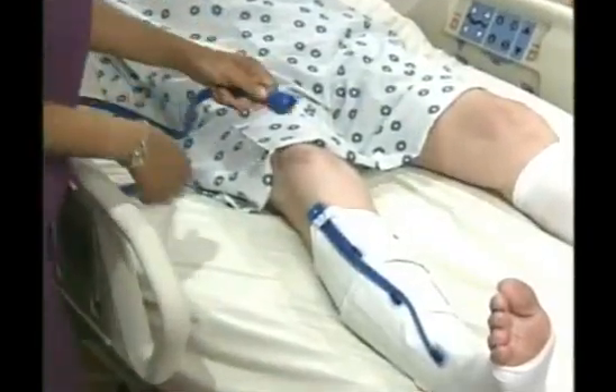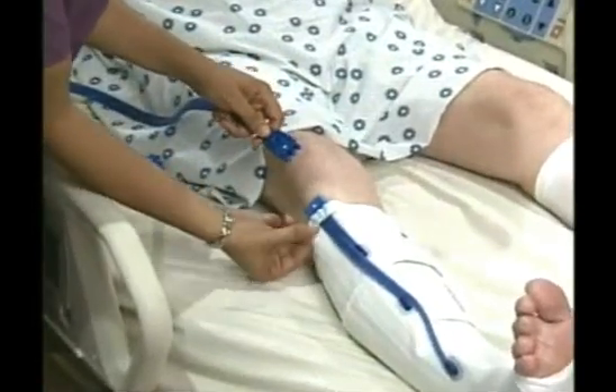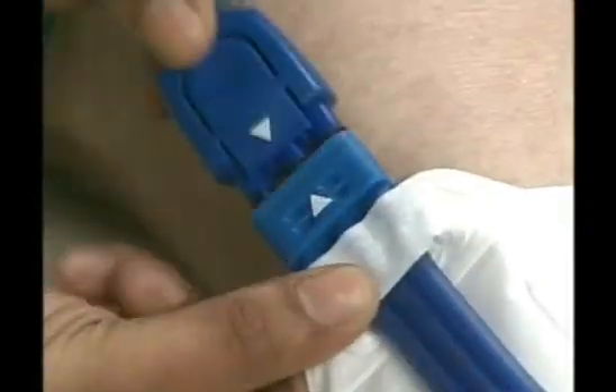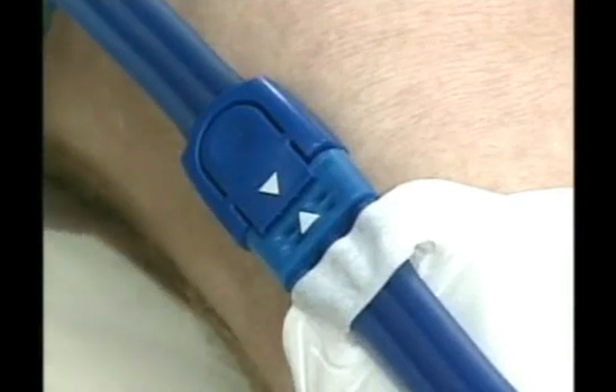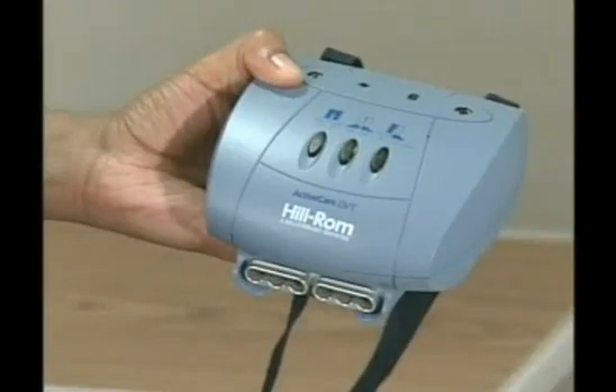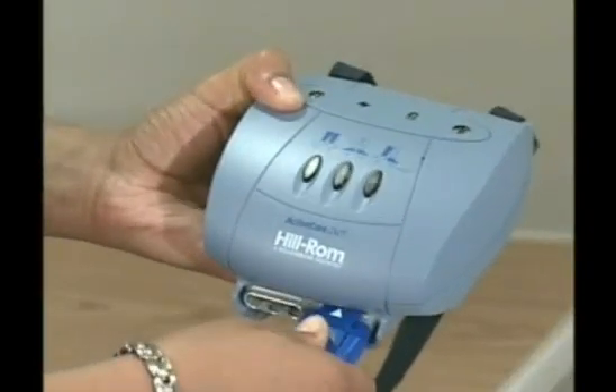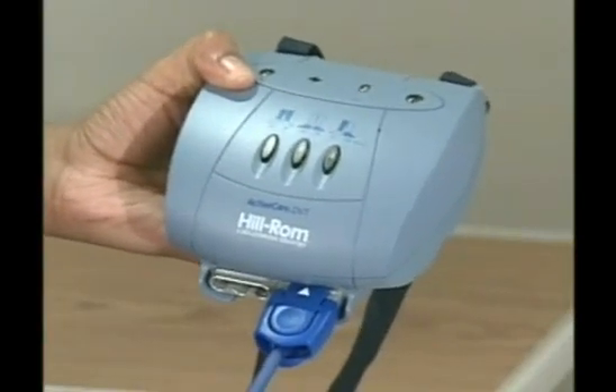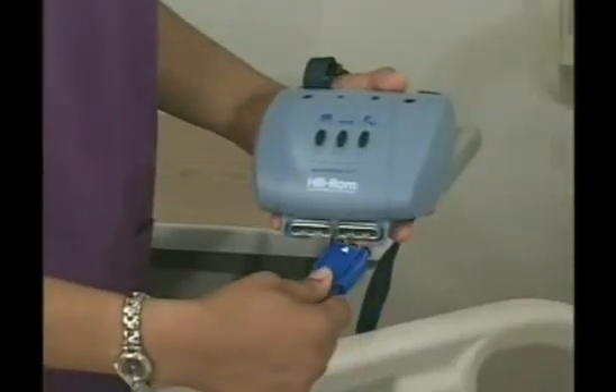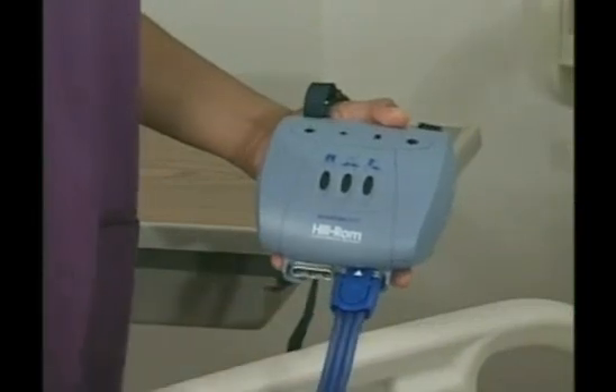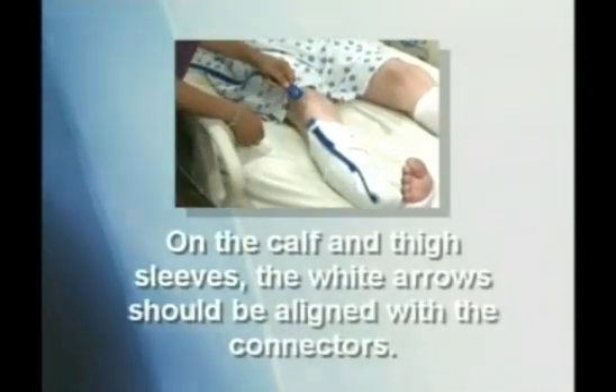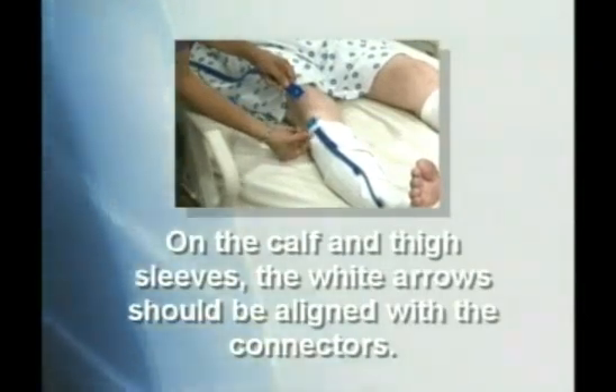Once the sleeve is properly positioned on the patient's leg, connect one end of the extension tubing to the sleeve connector with a white arrow facing up. Connect the other end of the extension tubing to the device, also with a white arrow facing up. An audible click will be heard when the connector is seated correctly. Note that on the calf and thigh sleeves, the white arrows should be aligned with the connectors.